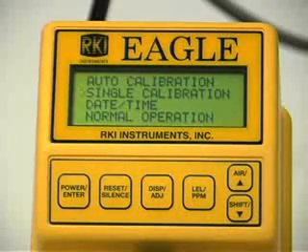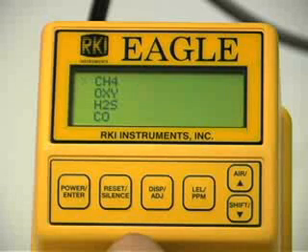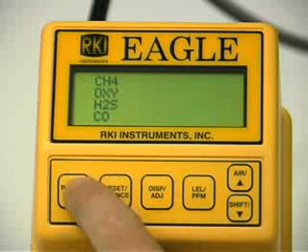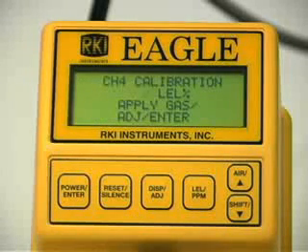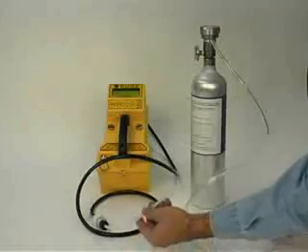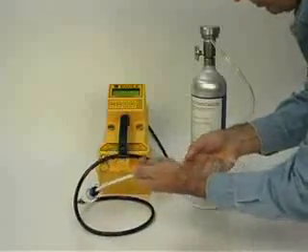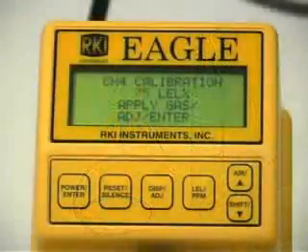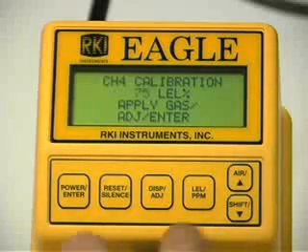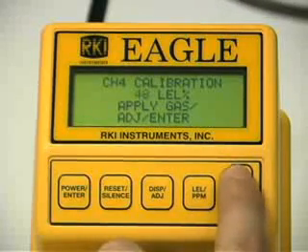Use the up and down button to place the prompt next to the single calibration menu option. Press the enter button to open the single calibration menu. Use the up or down button to place the prompt next to the channel to be calibrated, then press the enter button. The single calibration screen displays for the channel you selected and the gas reading flashes. Connect the tubing from the demand flow regulator to the EAGLE's probe. The EAGLE will immediately begin drawing in the calibration sample from the cylinder. Allow the reading on the EGLE's display to stabilize. If necessary, use the up and down buttons to adjust the reading to match the concentration listed on the calibration cylinder.